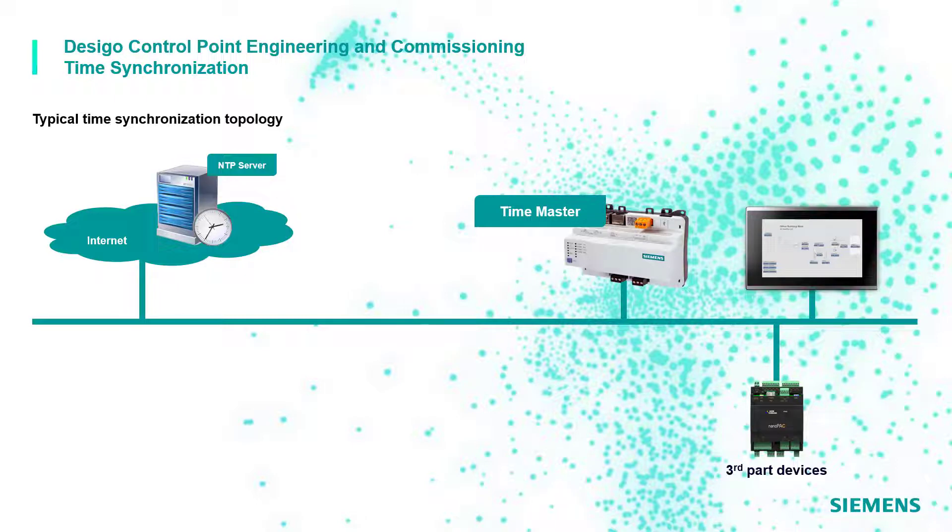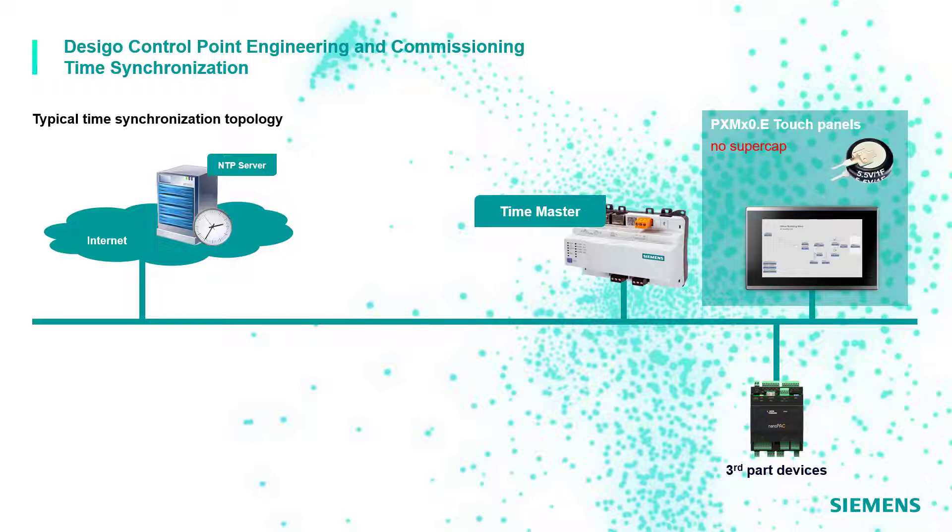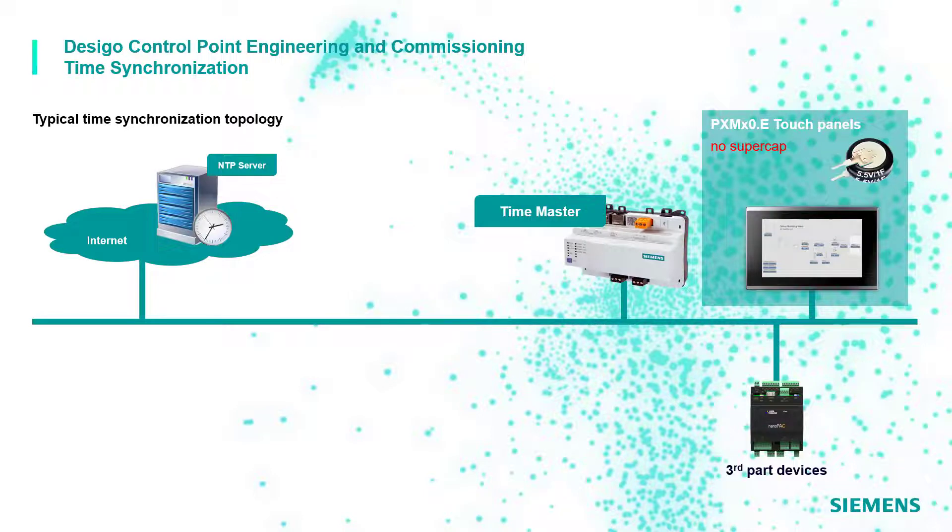However, the PXM touch panels are not equipped with a super cap, which would guarantee to keep the date and time information for a certain time if the hardware is powered off. For that reason, if no automation stations are available, it is always recommended to set the Time Master function on a PXG3 web server device, which is instead equipped with a super cap.